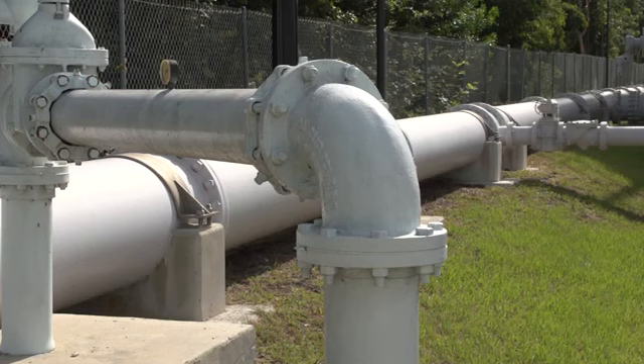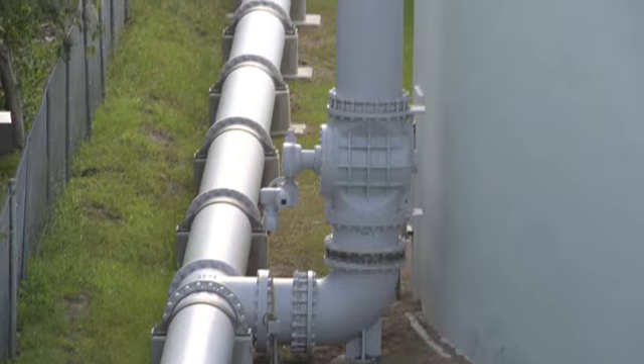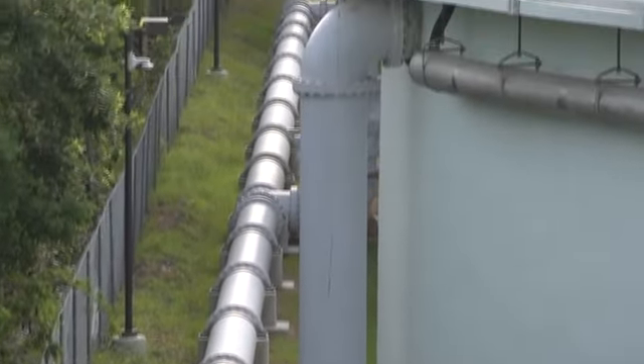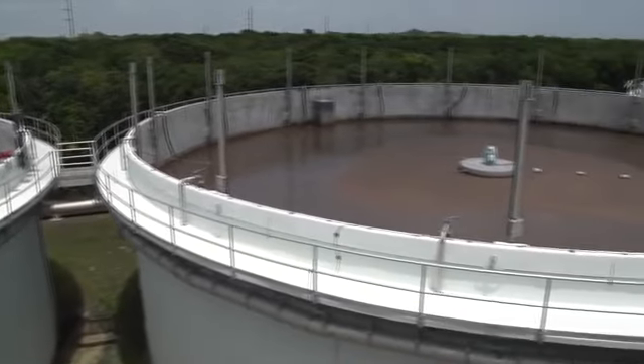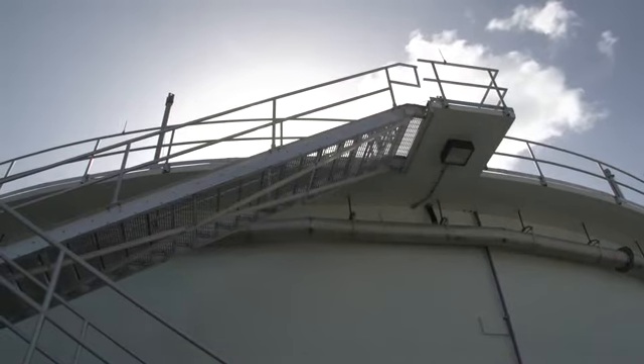We were slowly building up flows and adding areas step by step. Key Largo selected the AquaSBR sequencing batch reactor from Aqua-Aerobic Systems to meet these strict effluent requirements while providing process flexibility that results in energy savings. We actually started with a very low flow of 100,000 gallons per day or less and were able to treat to AWT standard at such a low flow. As the flows increased over time in the first year, we were able to divide the biomass into two tanks to accommodate the increase in flows over a year's time.